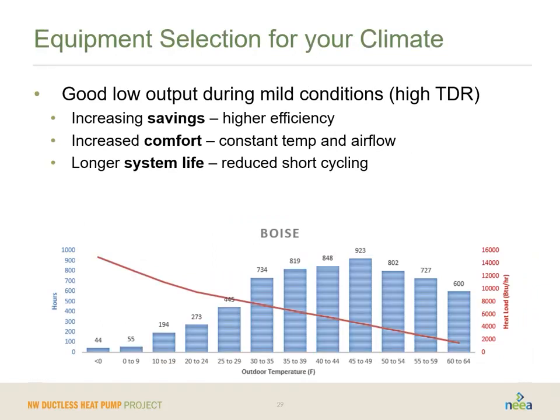So you really do want to think about selecting equipment that's appropriate for your climate. This good low output during mild conditions, or this high turn down ratio, is really going to be terrific for everything west of the Cascades and things east of the Cascades where you have a very efficient home. In those scenarios, you're going to get increased savings, increased comfort, and a longer system life. So it's an all-around series of wins. If you have a fairly well weatherized home east of the Cascades, or a newer home, or just about any home west of the Cascades, providing it's not at an extremely high elevation, you should be able to get by with a higher turn down ratio standard ductless heat pump.